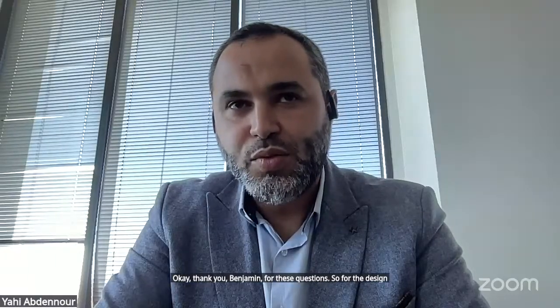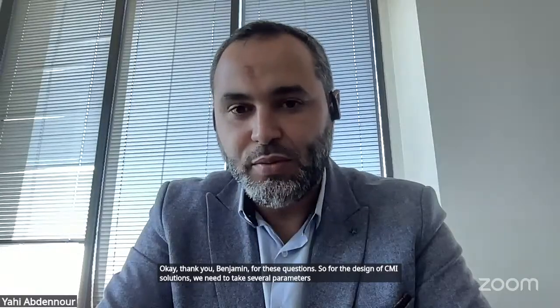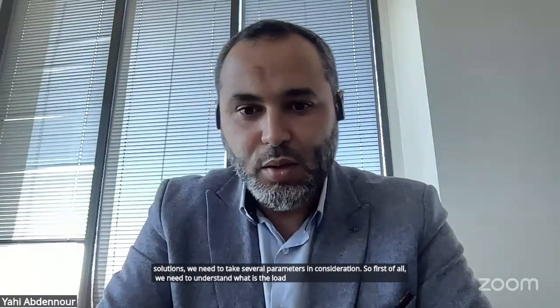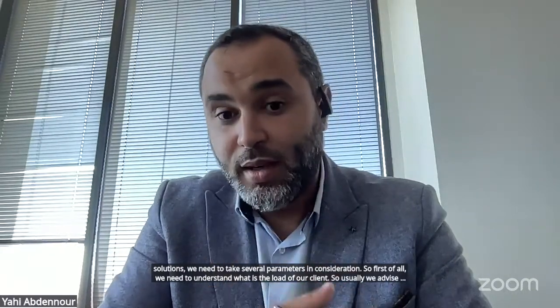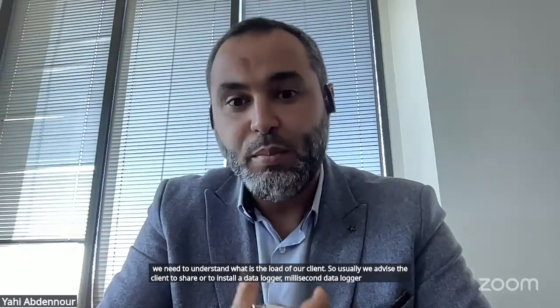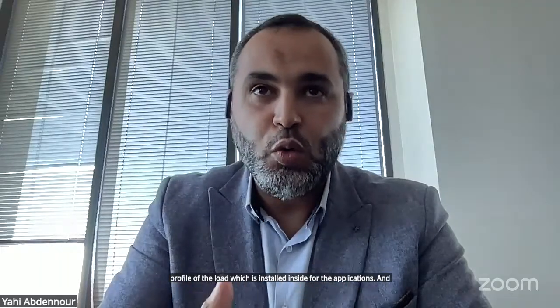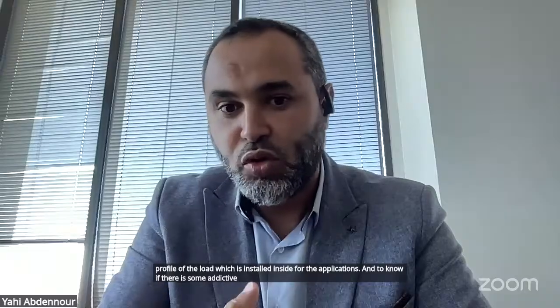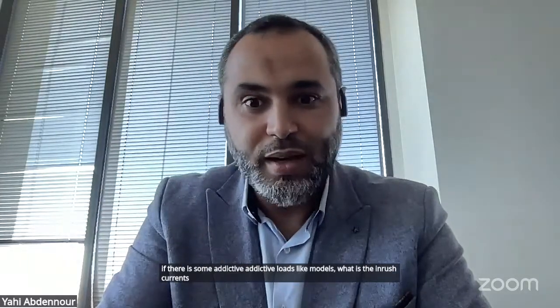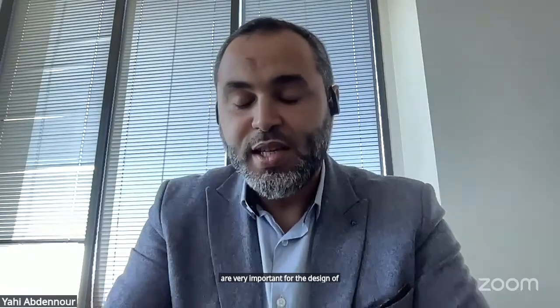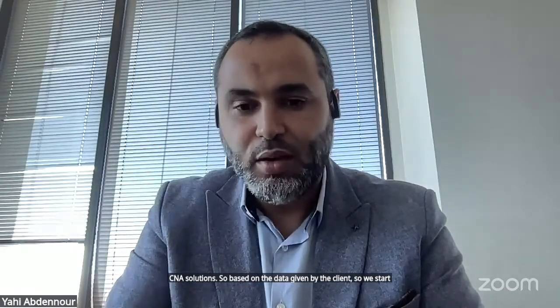Thank you, Benjamin, for these questions. For the design of C&I solutions, we need to take several parameters into consideration. First, we need to understand what is the load of our client. Usually we advise the client to install a millisecond data logger, so at least we know the profile of the load installed for the applications, and to know if there are inductive loads like motors, and what is the inrush current.